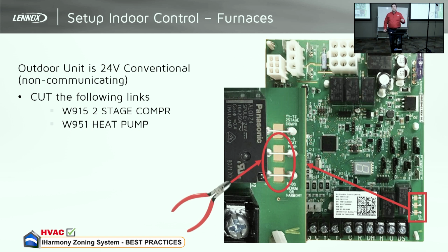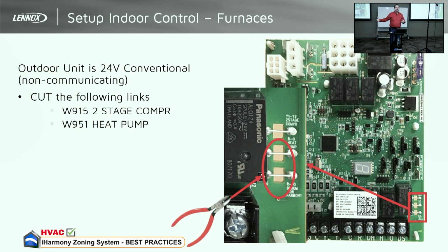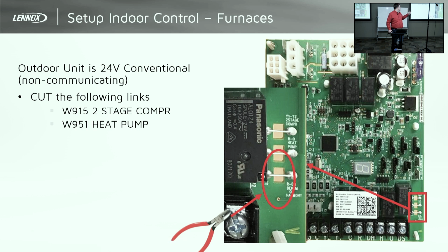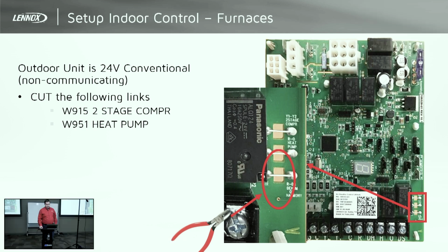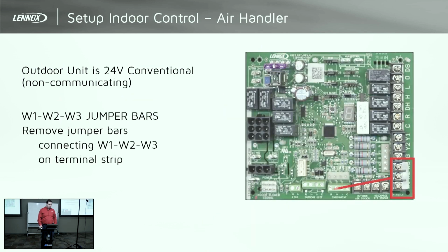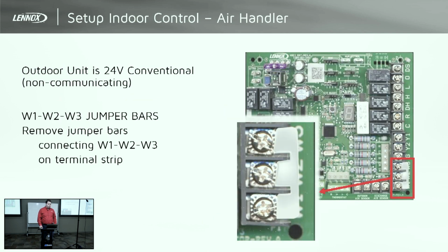If you're using a non-communicating outdoor unit, on these systems, you have to clip these jumpers. So if you've got a non-communicating heat pump or a two-stage system, you'll have to clip, for example, well, actually, because my mouse don't show up. That middle one is there for heat pumps. So if you've got a non-communicating heat pump, you clip that one. If it's two-stage, you clip the one at the top there. And you have to go through a function to add that as a non-communicating piece of equipment there on the S30.